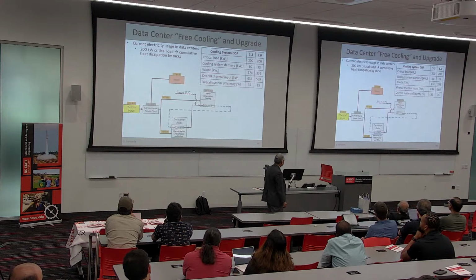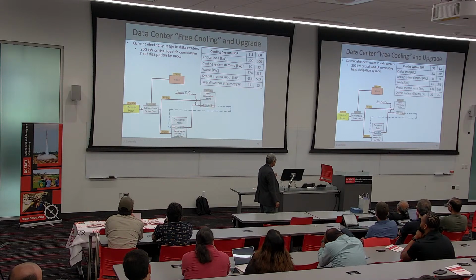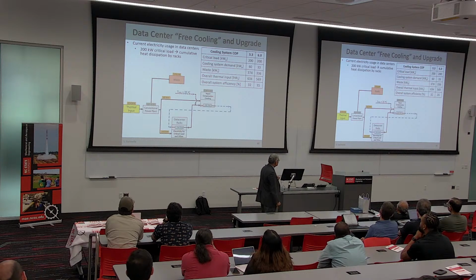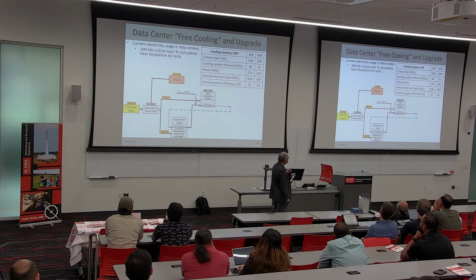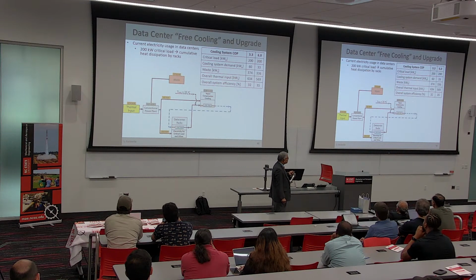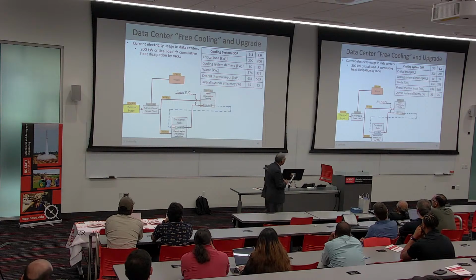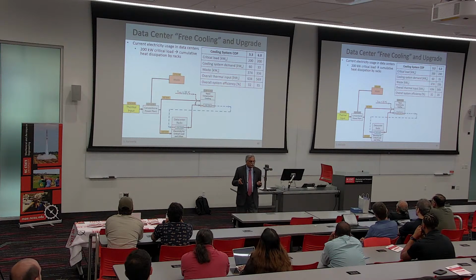Well, this is the state of the art: to be able to provide 200 kilowatts of critical load, you have to burn fuel to put in this much thermal energy. This much goes to waste. And then you have to run a vapor compression cooling system at a COP of 3.3 so that you can provide the cooling. But there's a lot of waste here. You're throwing away a lot. Can you do something with this?